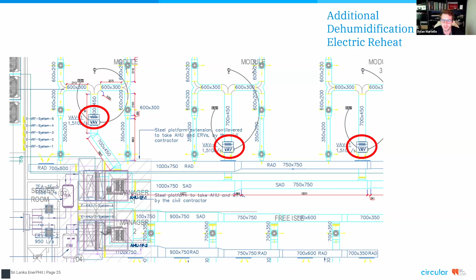By cooling it to that low a temperature, you're creating condensation, and that's what's wringing the moisture out of the air. Then you drain that moisture from the building with a condensate drain process. But that air is really cold, 55 degrees Fahrenheit. This is where the reheat comes in. If you're reheating with electric resistance, you're wasting a lot of energy, because you have so much heat in the building already. Is there a way to use that heat, as opposed to making heat with electricity to reheat that air? We quickly flagged this and said, this is going to use a lot of energy. We need to evaluate other options. So we did not go with this approach. Next slide, please.